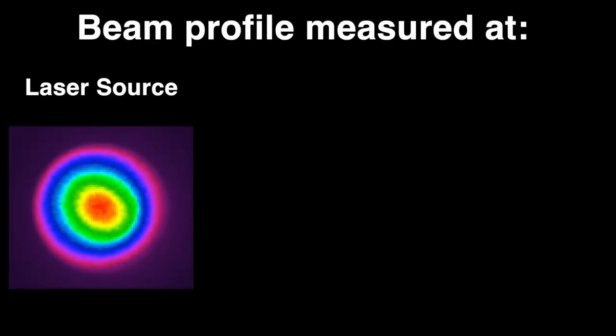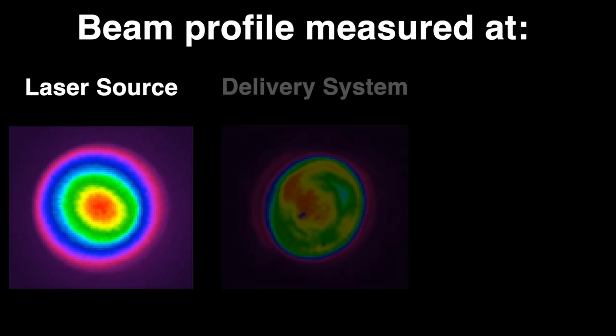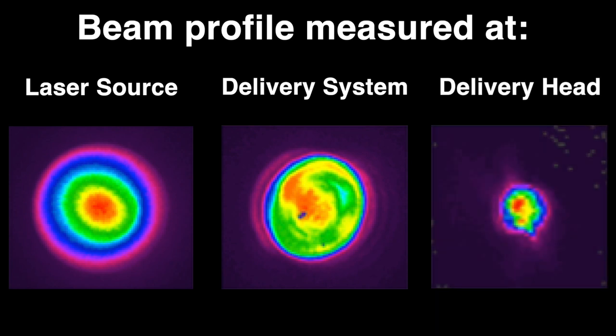MKS Ophir instruments answer these questions. In the example shown, a laser source is measured with BeamGage and a camera before transiting through the laser delivery system. A second beam profile is measured in the middle of the laser delivery system, and finally at the laser delivery head. Notice how the beam profile changes at different locations through the delivery path.